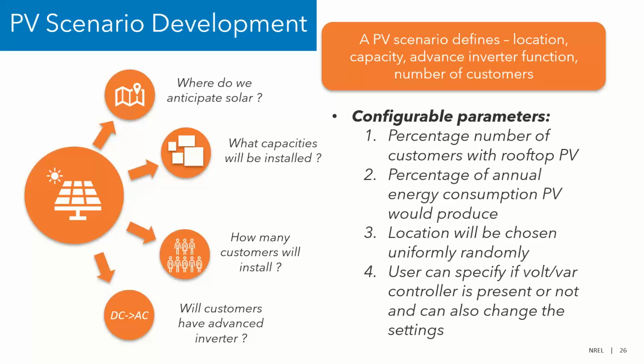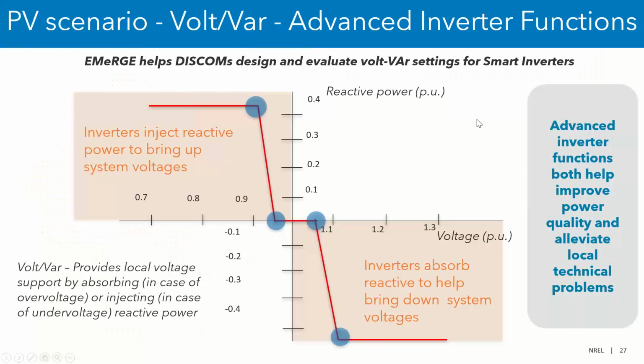Let me talk a bit about volt-var settings. Basically, volt-var settings allow PV inverters to either absorb or inject reactive power to provide voltage support at the point of connection. If the feeder is experiencing under-voltage, inverters can inject reactive power to boost the voltage. If experiencing over-voltage, they can absorb reactive power to bring the voltage down. In the EMeRGE tool, you can specify the voltage thresholds for when to start injecting or absorbing reactive power.